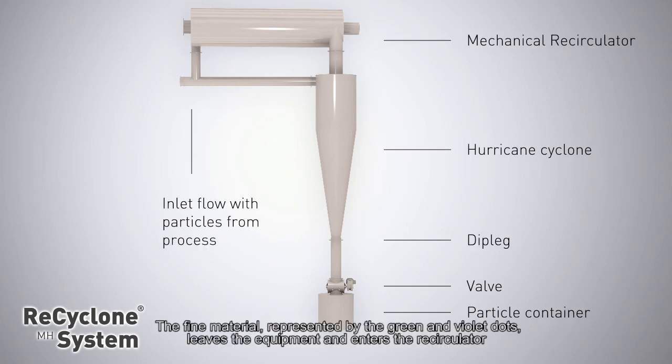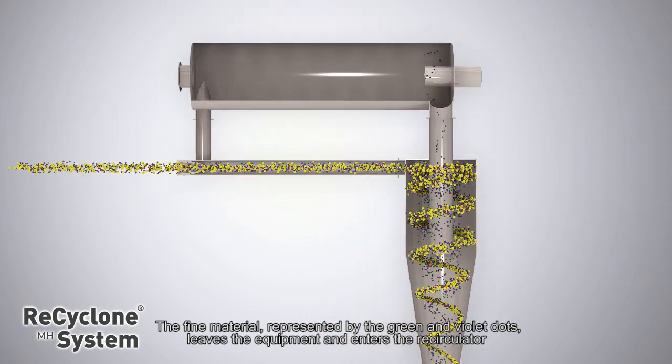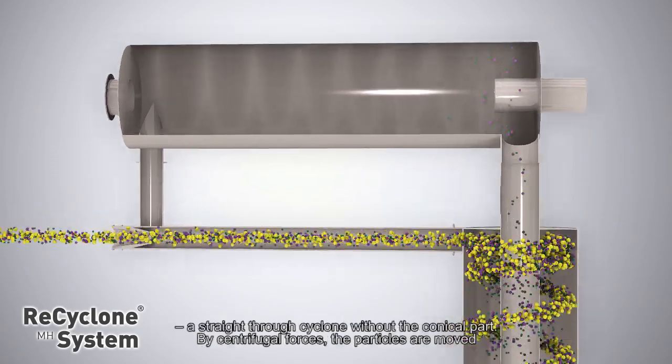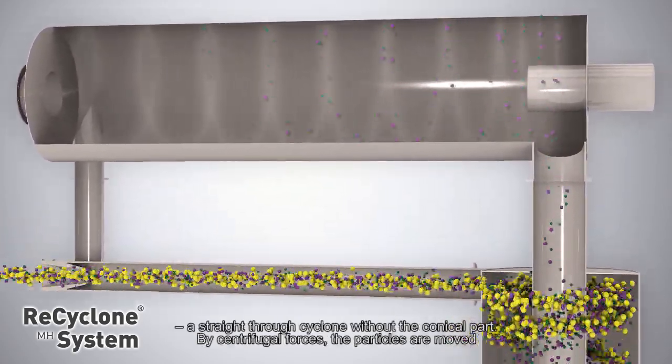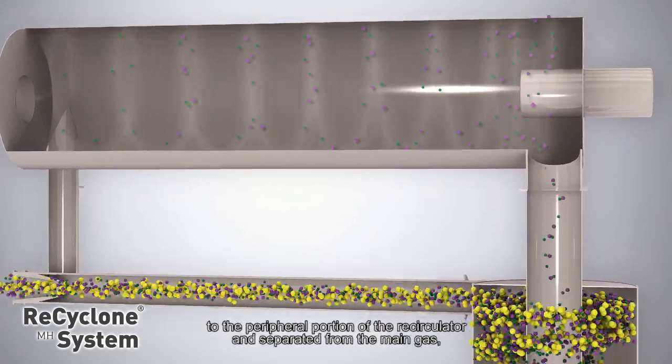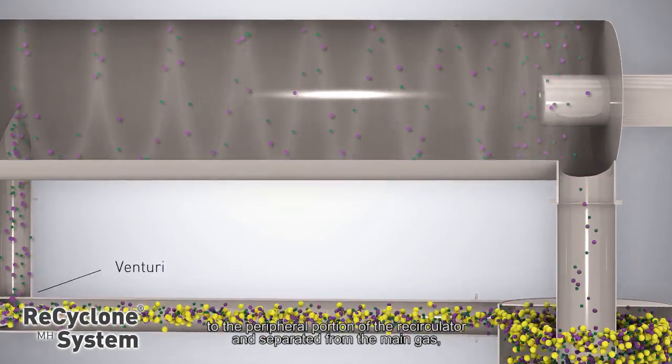The fine material, represented by the green and violet dots, leaves the equipment and enters the recirculator, a straight through cyclone without the conical part. By centrifugal forces, the particles are moved to the peripheral portion of the recirculator and separated from the main gas, which flows through the axis and exits the equipment out into the atmosphere.